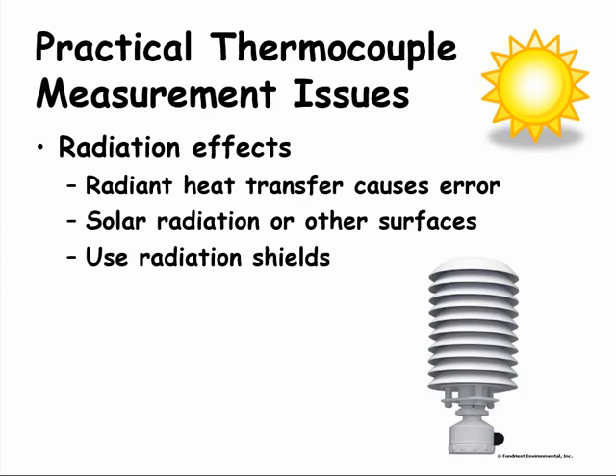Radiation effects can be mitigated by installing the temperature sensor inside a radiation shield. The figure here shows a radiation shield commonly used when measuring ambient temperatures. The radiation shield allows airflow past the sensors, and the white color reduces radiation effect.